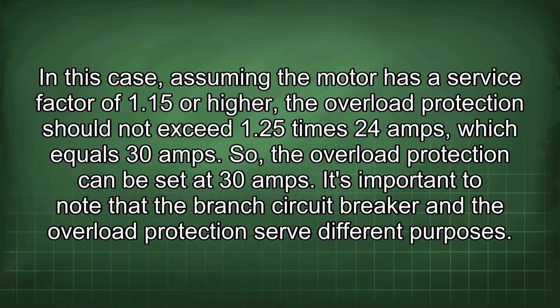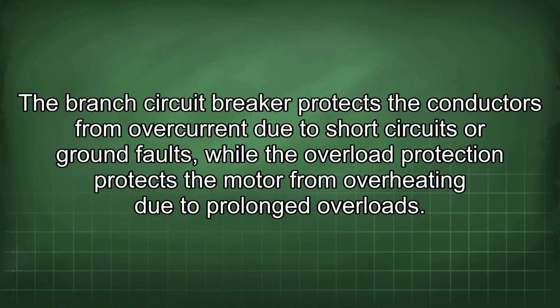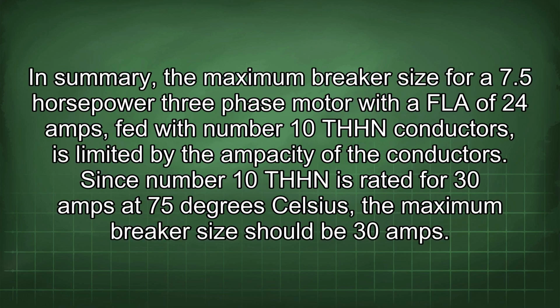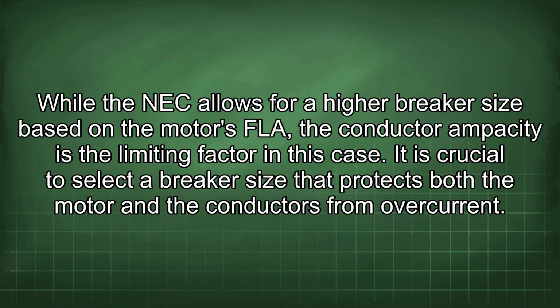It's important to note that the branch circuit breaker and the overload protection serve different purposes. The branch circuit breaker protects the conductors from overcurrent due to short circuits or ground faults, while the overload protection protects the motor from overheating due to prolonged overloads. In summary, the maximum breaker size for a 7.5 horsepower three-phase motor with a FLA of 24 amps, fed with number 10 THHN conductors, is limited by the ampacity of the conductors. Since number 10 THHN is rated for 30 amps at 75 degrees Celsius, the maximum breaker size should be 30 amps. While the NEC allows for a higher breaker size based on the motor's FLA, the conductor ampacity is the limiting factor in this case.